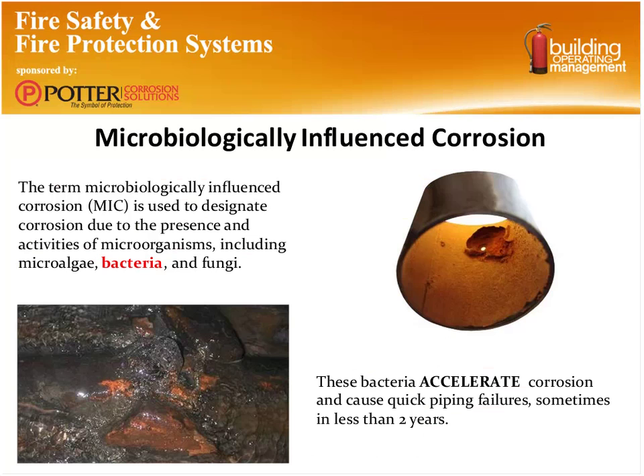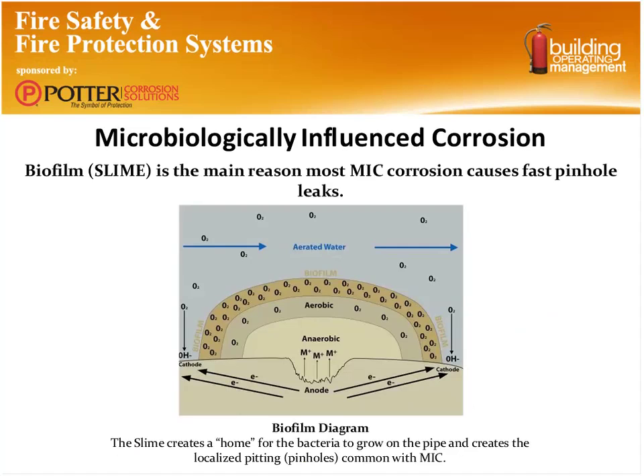So everybody says, well, what does that mean to me? Where do I have these issues? Well, it can be in both wet sprinkler and dry sprinkler systems, and we'll see that in a minute. But let's get you up to speed on what MIC, microbiologically influenced corrosion, is. Basically, it's a slime or bacteria or fungi that can either be oxygen-loving or operate in a non-oxygen environment, and will eventually create an atmosphere where it starts to consume the steel within the pipe.